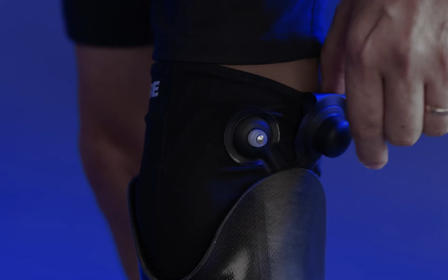To create a quick and a larger adjustment, the patient can inflate the system by connecting the external pump to the release valve. The user can also use the integrated pump for smaller adjustments throughout the day. To deflate, users will press the silver button situated on the exit valve. The air expansion system is placed in the back of the leg and covers about 2/3 of the residual limb. We ensured to place the air bladder on the pressure tolerant areas and where there is the most volume fluctuation, where also the soft tissues are.